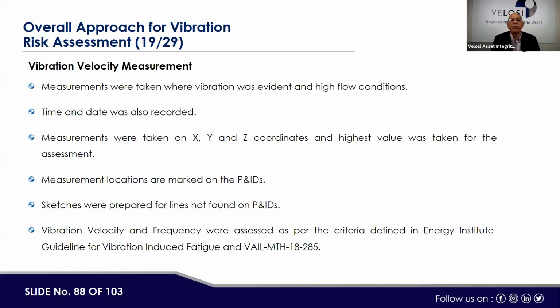Measurements were taken where vibration was evident and in high flow conditions. Time and date were also recorded. Measurements were taken on X, Y, and Z coordinates, and the highest value was taken for the assessment. Measurement locations are marked on the P&IDs. Sketches were prepared for lines not found on the P&IDs. Vibration velocity and frequency were assessed as per the criteria defined in the Energy Institute guidelines for vibration induced fatigue, and the velocity procedure.